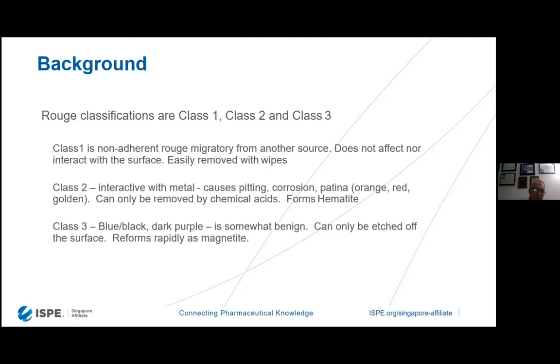Class 3, though, on the other hand, is dark blue or black and purple-ish color, and it is somewhat benign. It actually formulates almost an annealing effect on the inside of piping, and its formulation is magnetite. Magnetite being a more complex ferric oxide than even hematite. Hematite is Fe2O3 and magnetite is Fe3O4. Magnetite, though, rapidly forms in hot water, superior hot water, and hot water that is usually at different levels, including superheated water and steam. And if you open up your pure steam systems, most likely you'll see magnetite.